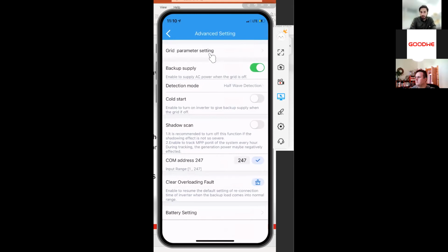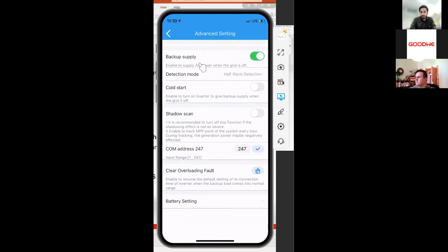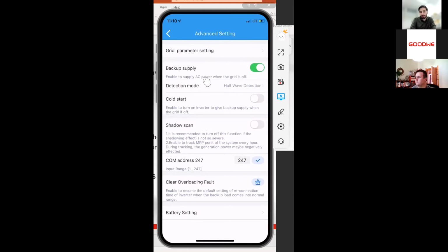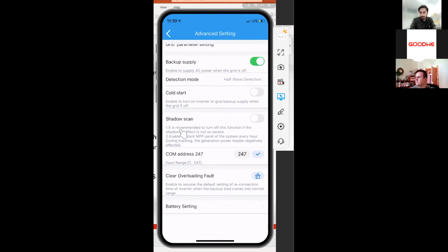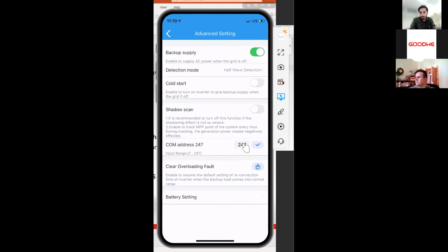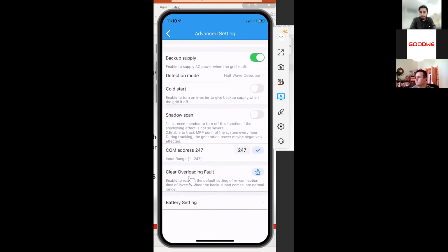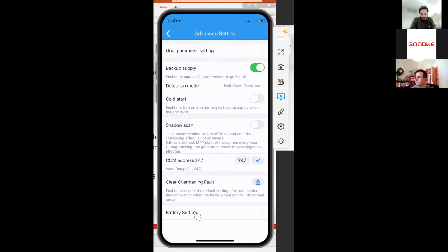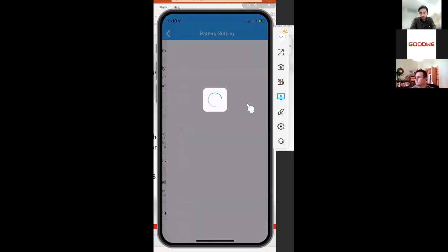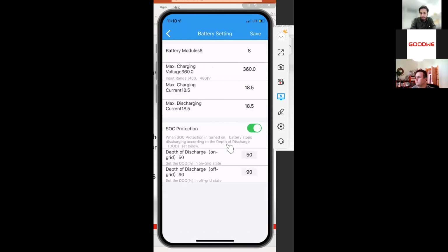Going back here, you see in advanced settings that here you have the backup supply. Here, the detection mode is maybe not very important. Cold start is also for very specific cases. Here you have the shadow scan again that I told you about previously, the COM address, and clearing the overloading fault. Interesting might be the battery settings here. We currently do not have a battery connected, but you can anyway see the standard battery settings or from the previous battery that was connected.